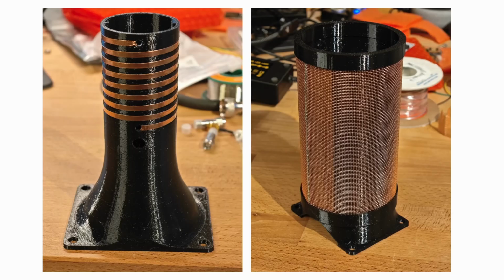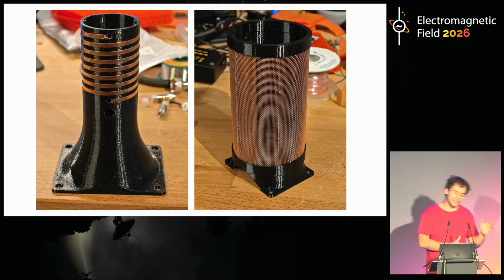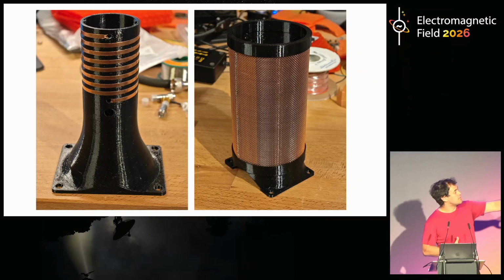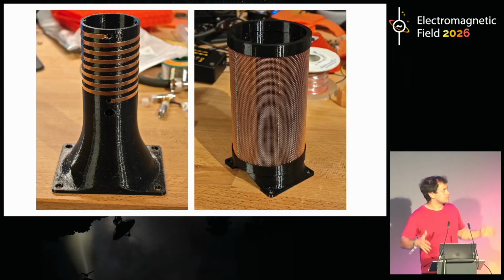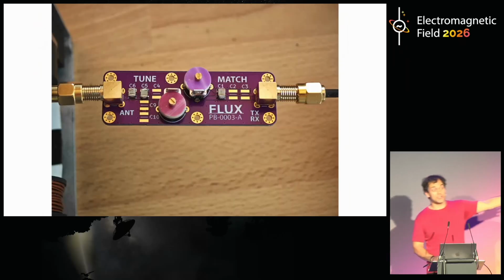And then you've also got this shield that we used for some experiments. You're in a Faraday cage, but you've also got your gradients, which will give you a bit of noise and antenna. So if you put a shield around your coil, you'll also reduce the amount of noise that's there. And these coils, one of the reasons we can make them work is we need a tuning circuit.